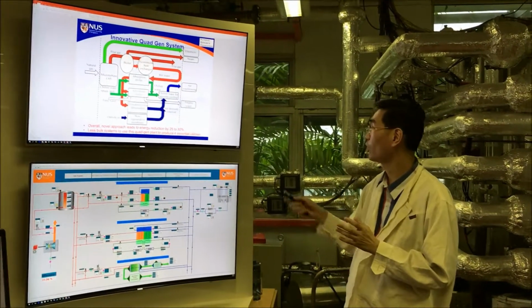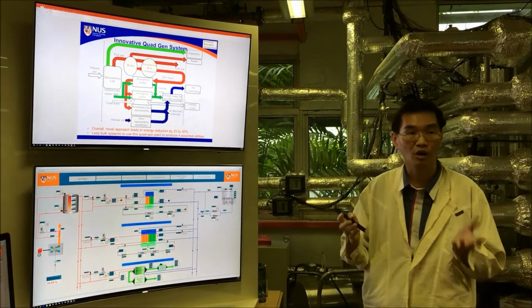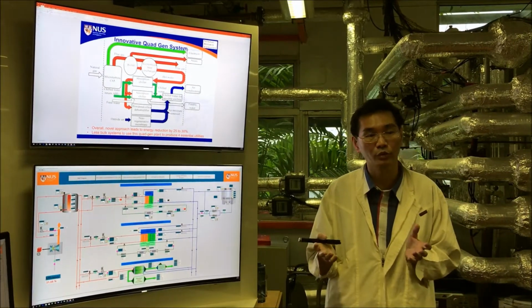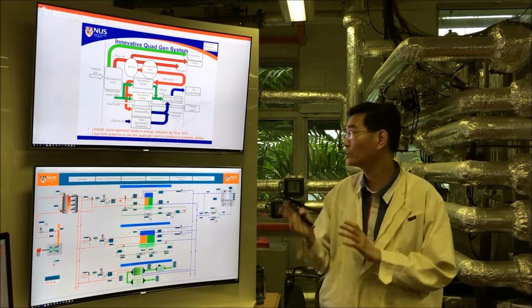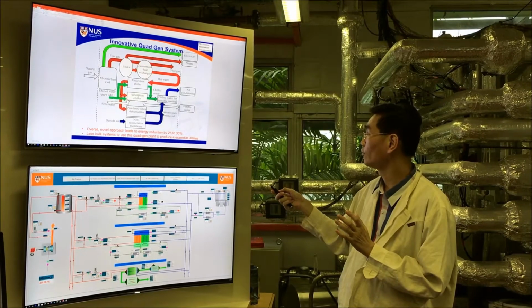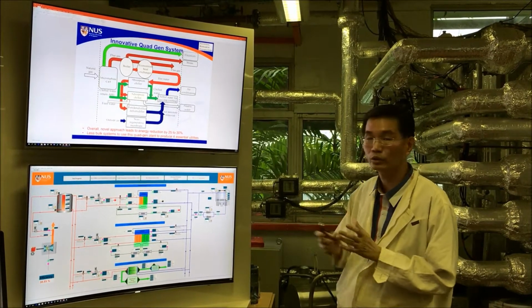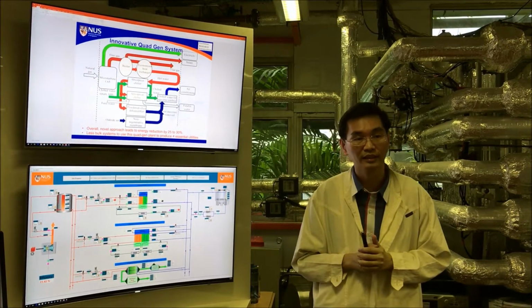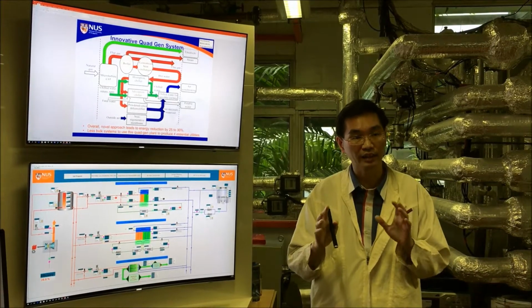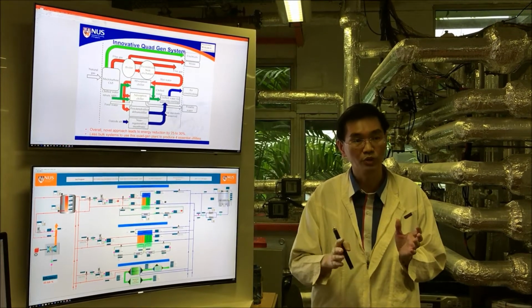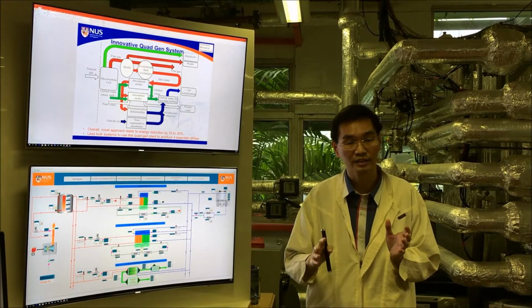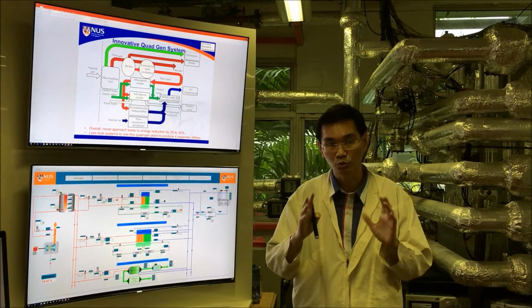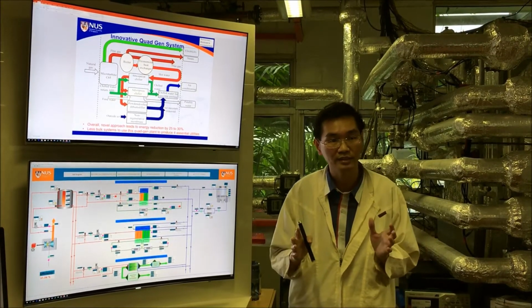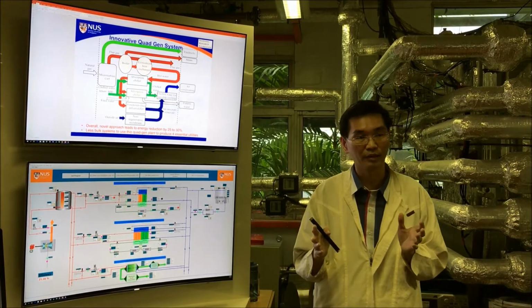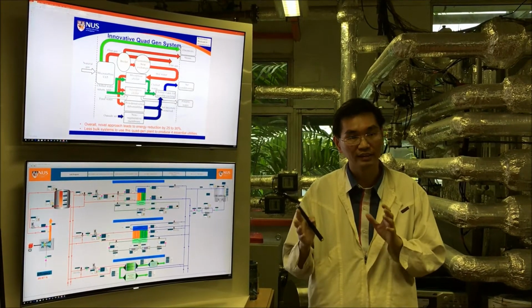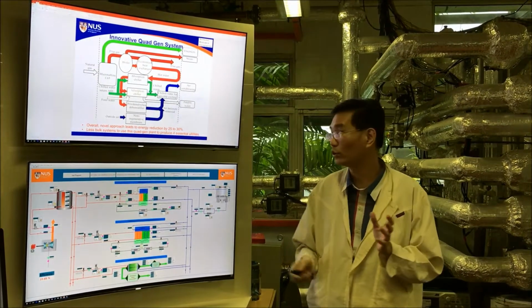So after producing steam or hot water, the flue gas is still of very good quality. The waste heat from the flue gas is very high quality. So we inject this flue gas via hot water system to the first stage absorption chiller. Absorption chiller takes in heat at about 90 degrees C to produce chilled water at about 6 to 8 degrees. So this absorption chiller is a 2-stage system designed in NUS and developed through a vendor. And these systems will enable us to produce the chilled water.